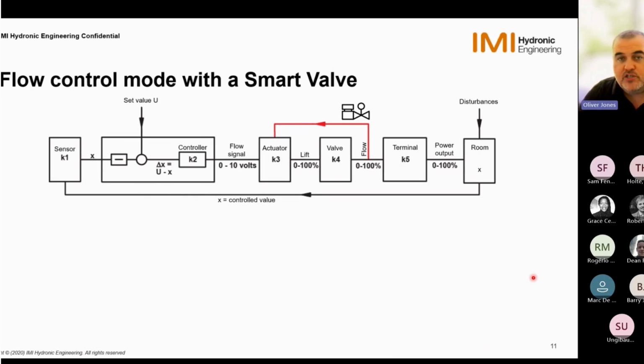So if we look at the smart valve and what it does in this type of control, it's the same as before, but with one exception. If we consider the black box that's shown on screen as the smart valve, there is a sub-control loop that's taking place locally. Now, this sub-control loop is measuring the flow and feeding it back to the actuator with a new target, so that the actuator will try to reach the flow as received by the controller, and this is what is changing, because now the input received from the controller is no longer a position signal, it's a flow signal. So when we get 10 volts, we should get to the maximum flow for this terminal unit, and when we get 5 volts, we should get to half of the flow. So the smart valve with a sub-control loop will, in a relatively fast way, within a few seconds to a few tenths of a second, adjust the flow as you want to get it.